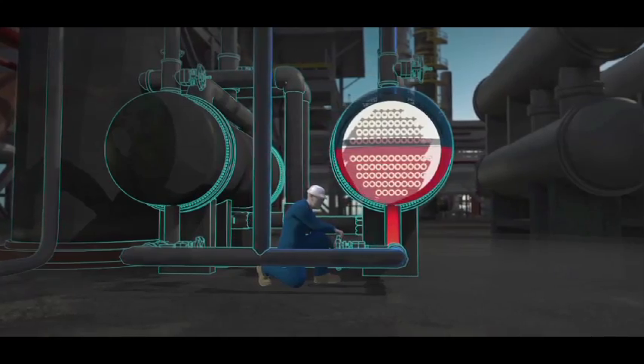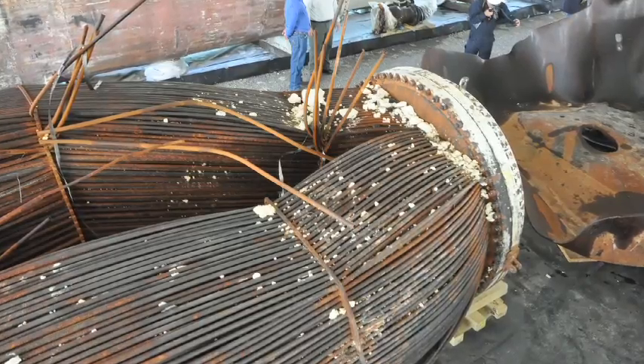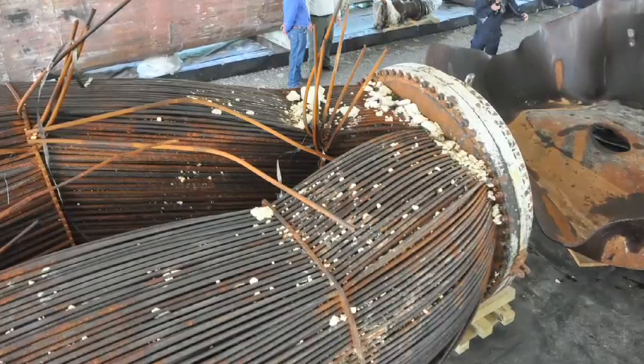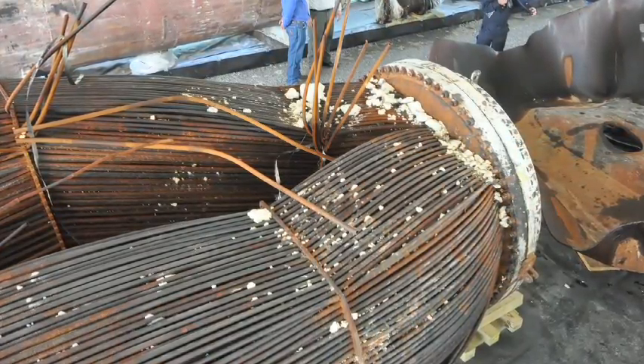One of the key lessons from this incident is the importance of detail when implementing process safety programs. If a critical detail is overlooked in an MOC, in a PSSR, a safeguard evaluation, or a PHA, a significant hazard can be missed, and this can lead to a major incident, sometimes years later. At Williams, the overpressure hazard was overlooked in that very first MOC, and that contributed to the explosion that occurred 12 years later.